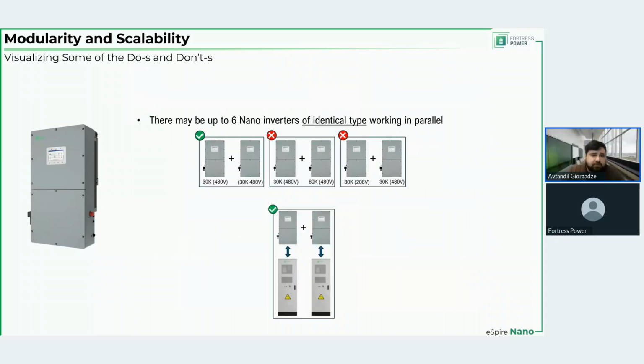So here, for example, you have a 30 kilowatt 480 volt inverter and a 30 kilowatt 480 volt inverter. They're identical type and they can work together, but you cannot mix 30 kilowatt 480 and 60 kilowatt 480. Same goes for the same AC output inverters. On this last one here, you see that there are two 30K inverters, but one is for 208, the other is for 480. They cannot be mixed.